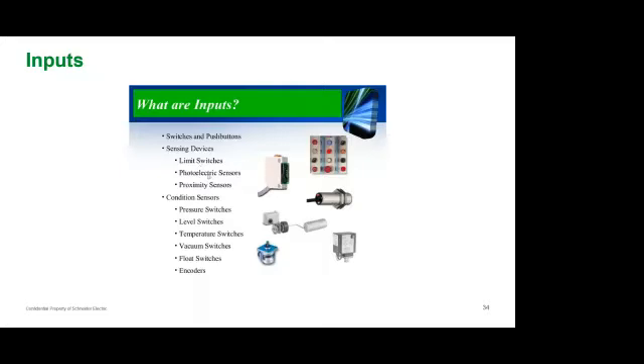Photoelectric sensors are optical sensors. So light is the operational unit here. A beam of light will be transferred to a reflector, and this light will continuously be transferred. When some object comes between these lights and disturbs the light transfer, a signal is sent to the PLC. Proximity sensors, as I told before, are metal detectors.